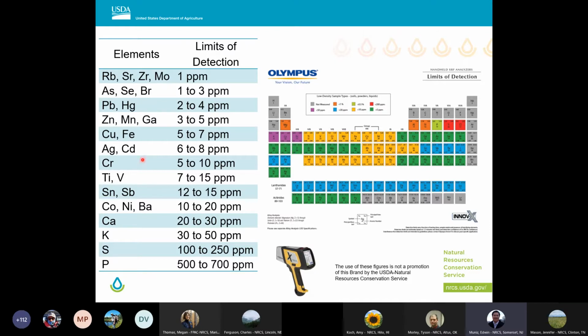So that means that when we're looking at lead, the cleanup standard for lead in New Jersey is 400 ppm. So you can see the limit of detection is 2 to 4, way lower than what I need. So these ranges work very well for both arsenic and lead. This is one of the things you have to keep in mind, the limits of detection of the equipment, depending on the kind of studies that you want to do. So make sure that the equipment can read the concentrations.